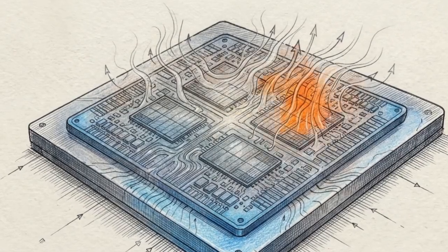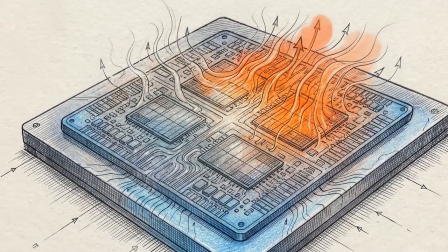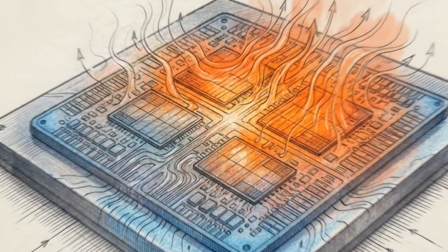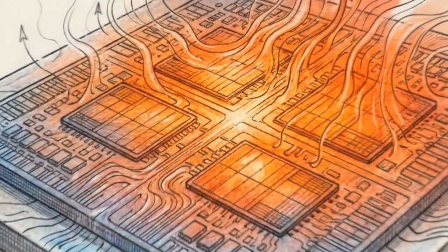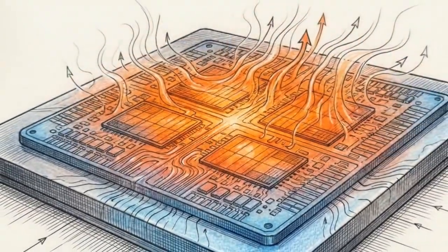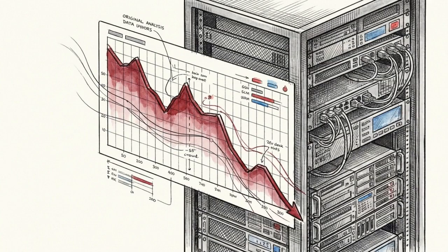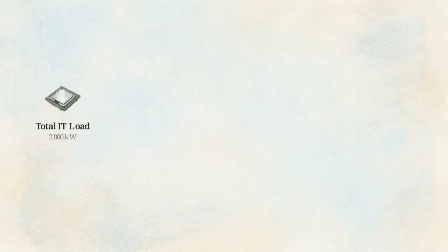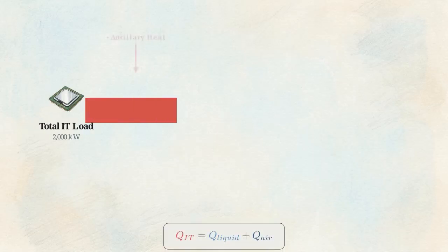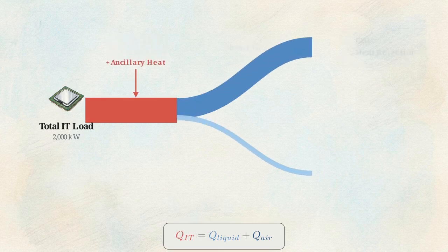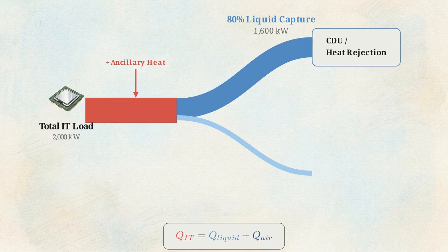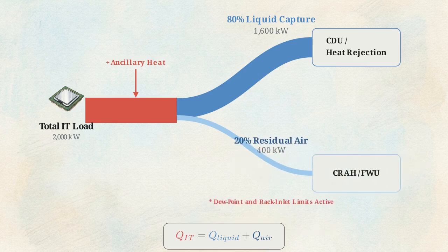Modern AI workloads generate extreme, concentrated thermal loads. At scale, a high-density cluster requires the continuous removal of up to 11.35 megawatts of heat. If that thermal energy isn't extracted instantly, the processors will thermally throttle. To solve this, engineers rely on a strict heat split rule. The total IT load, plus any ancillary equipment heat, must be divided into two removal paths: liquid capture directly at the chip and residual air capture in the room.